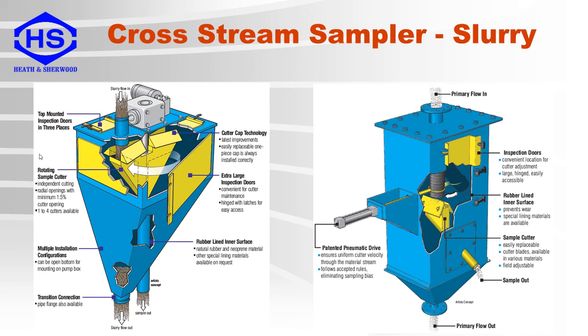These are two other types of cross-stream samplers. They can be used as primary samplers depending on the process flow, or as secondary or tertiary samplers. Both are connected to a vertical pipe where the process slurry comes from the top and discharges out the bottom. The one on the left is a rotary Vezin sampler, where the cutter rotates across the incoming slurry stream. The one on the right is a moving inlet sampler, where the hose is moved across the cutter.